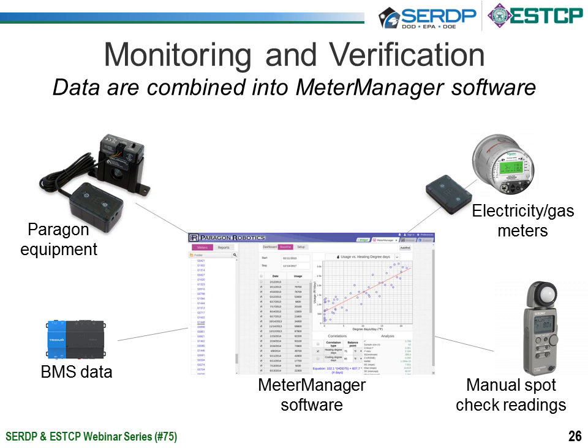The key advantage of doing this is that these ESCOs need to verify that everything is working properly, and the faster they can catch problems, the faster they can turn around and fix them and make sure there's no issues. So MeterManager can be set up with automatic alarms and complex algorithms to be able to take data daily and alert the ESCO or operations and maintenance personnel on site there to any problems that would affect the energy usage.